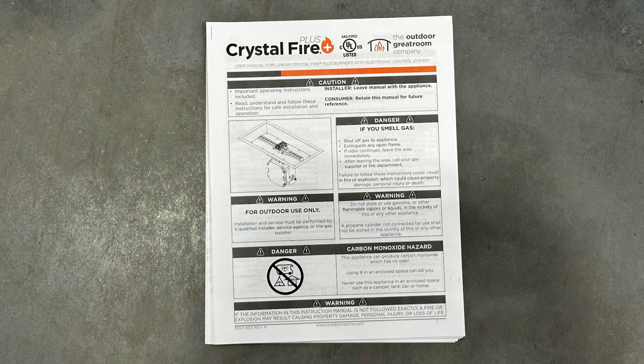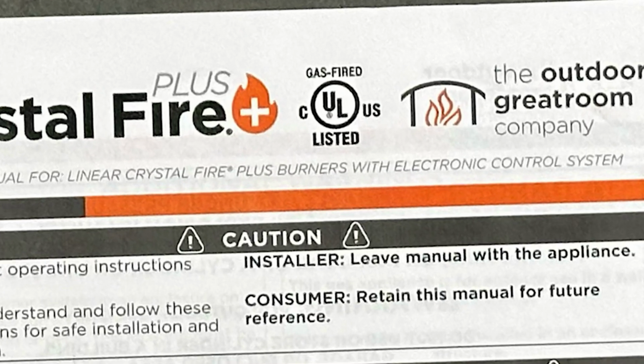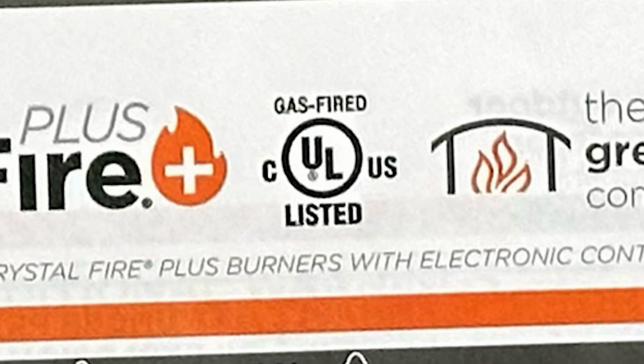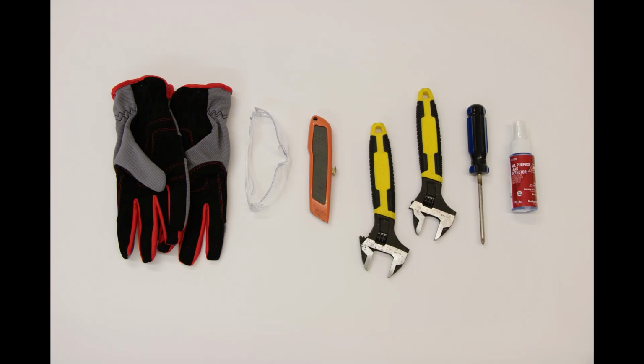All Crystal Fire Plus electronic ignition burners are UL tested and approved, and the feature content of these burners makes them perfect for commercial and high-end residential applications. To begin, you will need the following tools for setup work: gloves, safety glasses, a utility knife, 2 adjustable wrenches, a Phillips screwdriver, and a leak detection device or solution.